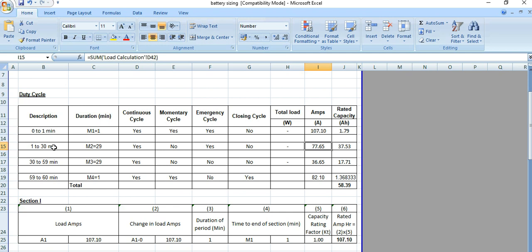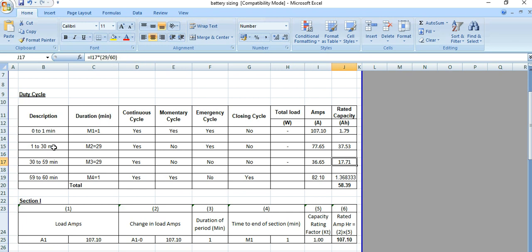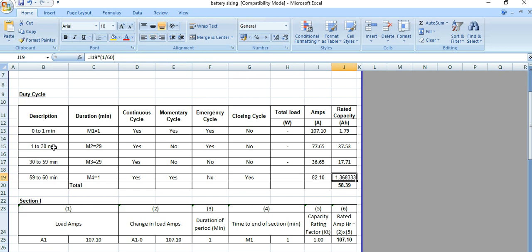Next is the 30-to-59 minute load, so M3 equals 29 because it is a 29-minute duration. Here we have only continuous load — no momentary, no emergency, no closing load — which is 36.65, multiplied by 29/60. Next is the last minute, M4, from 59 to 60 minutes. Here we have continuous load, momentary load, and closing load but no emergency load, coming to 82.10, multiplied by 1/60. Summing up all four gives a total of 58.39.